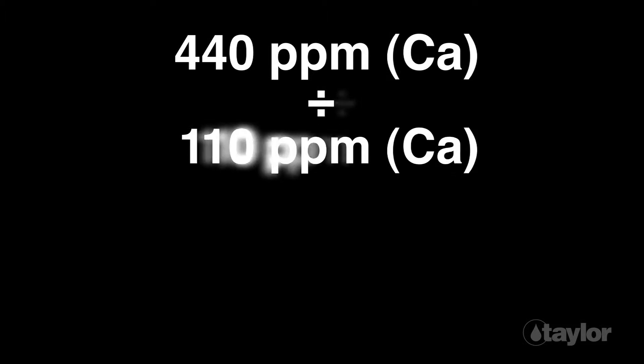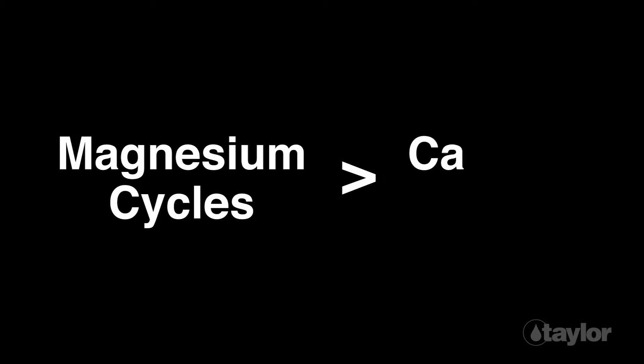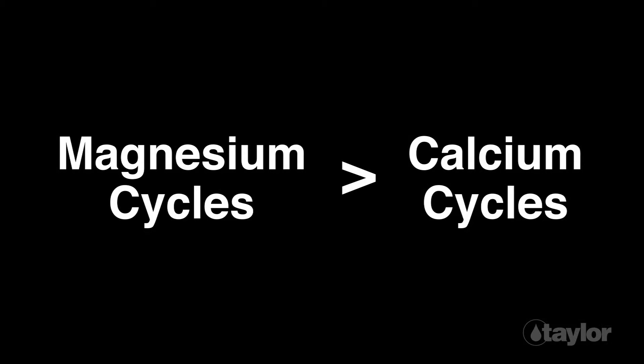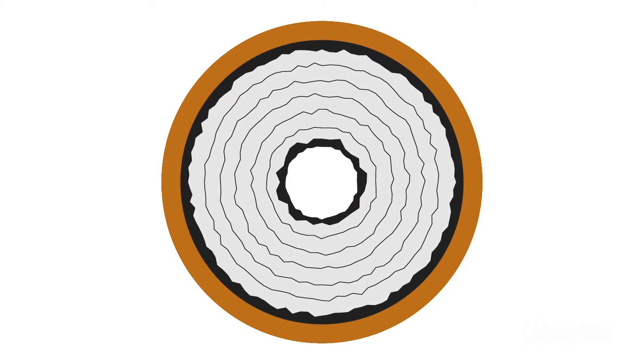If this value is similar to that found when dividing the cooling water calcium level by the makeup water calcium level, then you can be reasonably assured that your system is not forming calcium scale. However, if the value from the magnesium calculation is noticeably higher than the calcium calculation, then the system may be experiencing calcium scale formation.